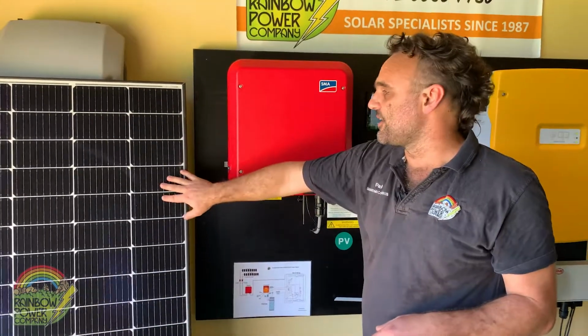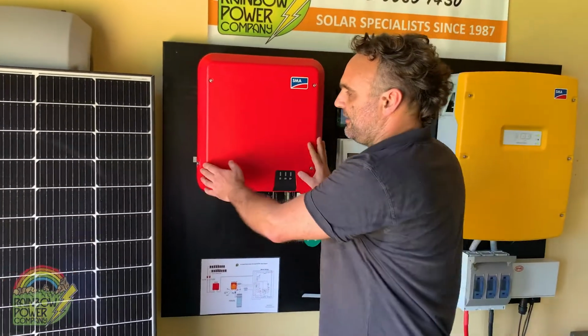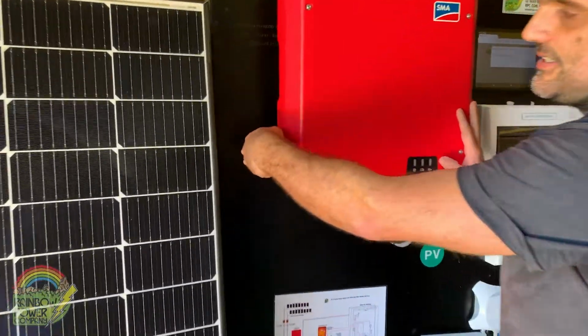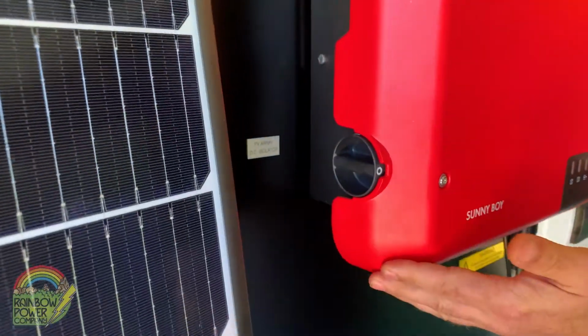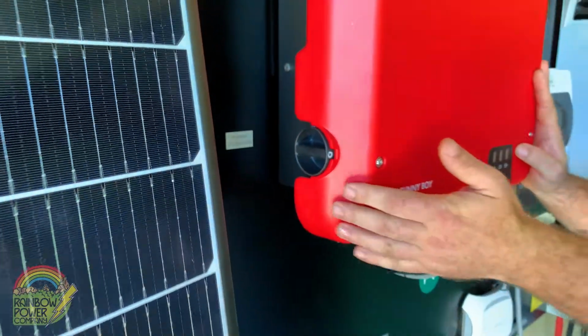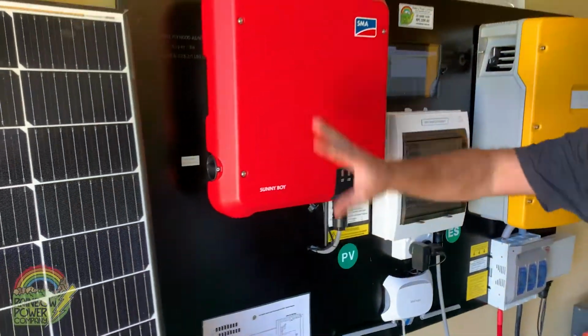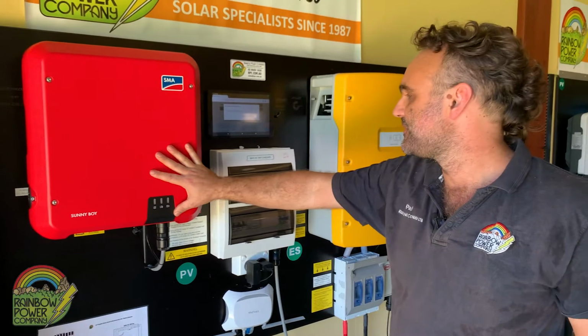Next, we're going to stop the solar coming into the solar inverter, and we do that by turning the DC isolator off on the side of the Sunny Boy inverter. Once this is off, we no longer have power flowing into the system from the solar panels.